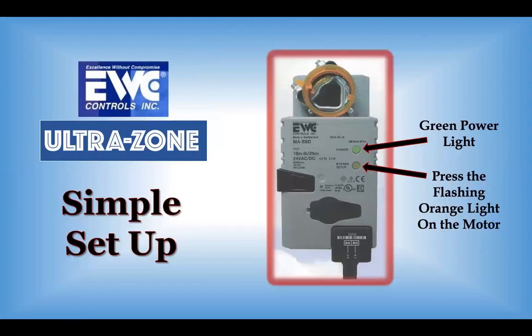Once we have that in place, we turn our blower on, put it on the highest operating speed for that system, make sure all of our zone dampers are open, make sure our air filter is clean. We want optimum static readings. Give that system 5 to 10 minutes to pressurize. You'll come over to that motor and you'll see a constant green power light. Below that, you will see a flashing orange light.